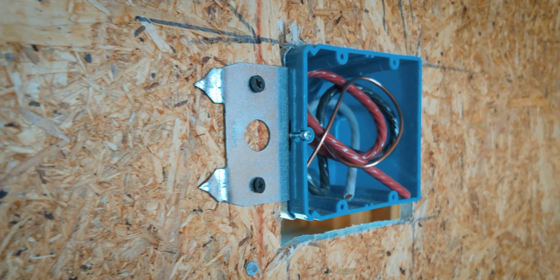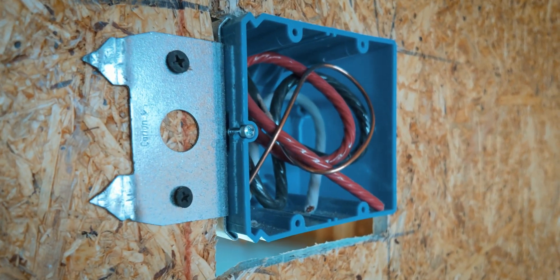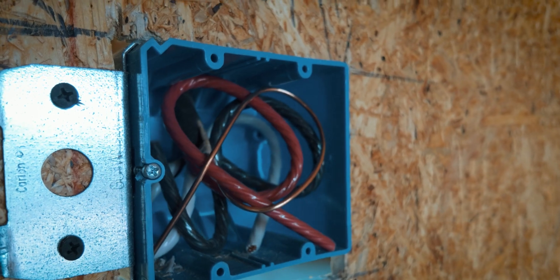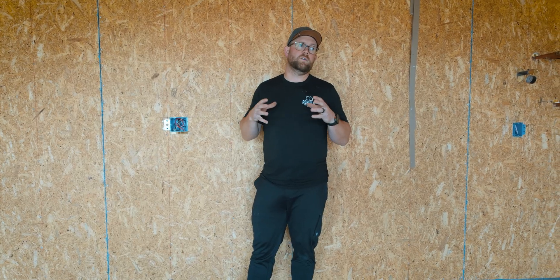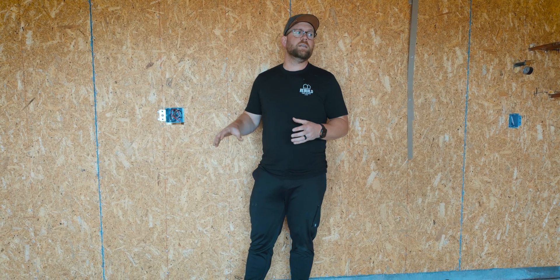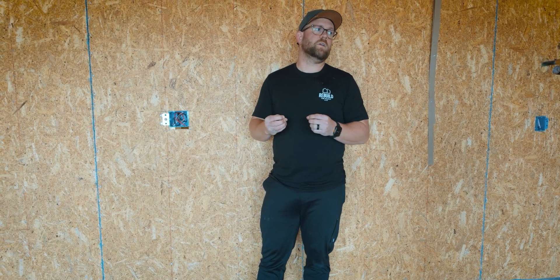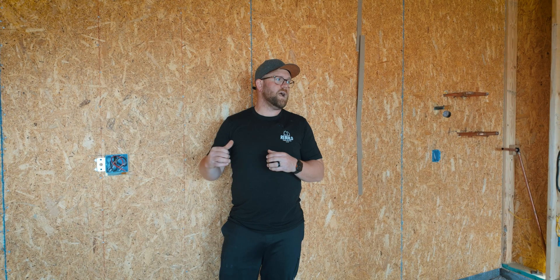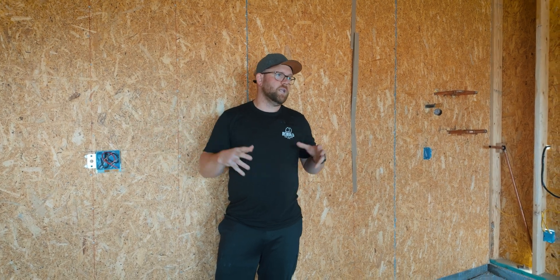These days, architects and electrical engineers are actually putting two car charging dedicated circuits into many new luxury builds. This increases the draw from one 50 amp circuit to two 50 amp circuits, which has a massive impact on the overall power coming off the grid. Couple that with kitchen appliances, the HVAC system, laundry, and other dedicated circuits throughout the home, and you quickly reach that threshold of 200 amps or more.